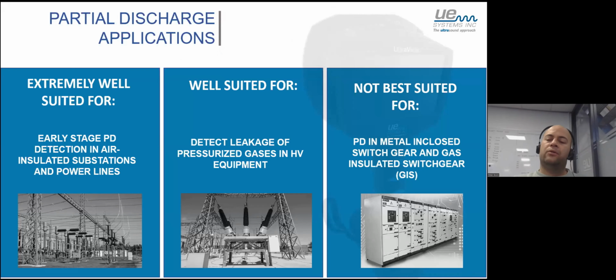All right, so where can we use the camera? What's the best field for electrical inspection with the camera? Well, of course, partial discharge in substations, open electrical assets, bus bars, switchgear, dry transformers. You can also use it for SF6 gas insulators when they're pressurized - when there's an SF6 gas leak, and it's not very windy, then you can find it. Where I would not use it is for gas insulated switchgear, the GIS systems - that's not going to work. It needs to be airborne so you can find it and see it.